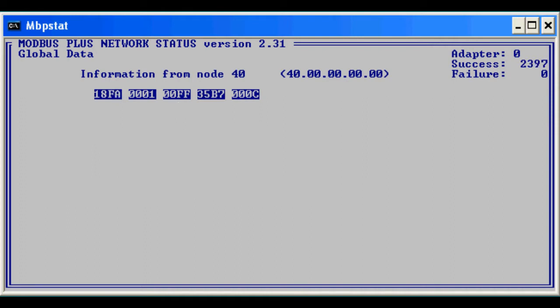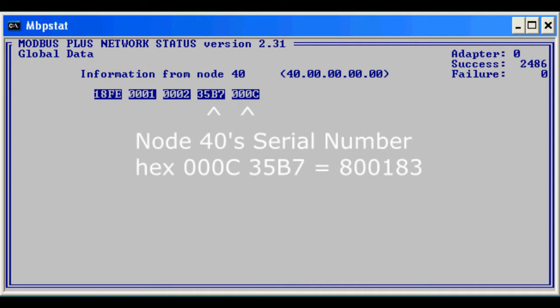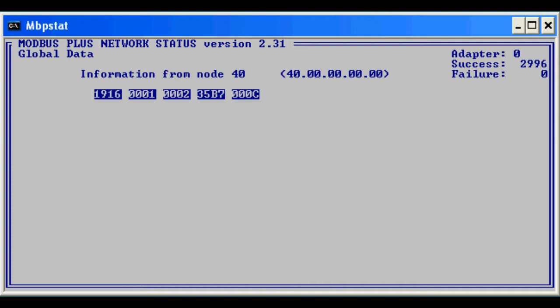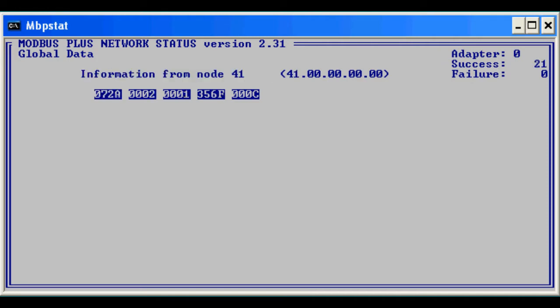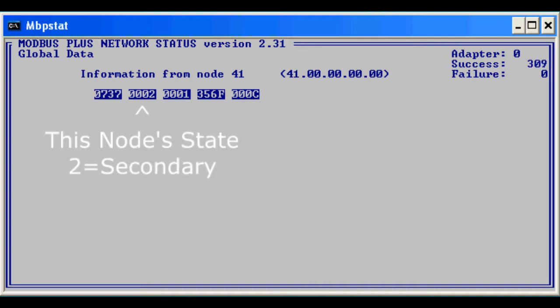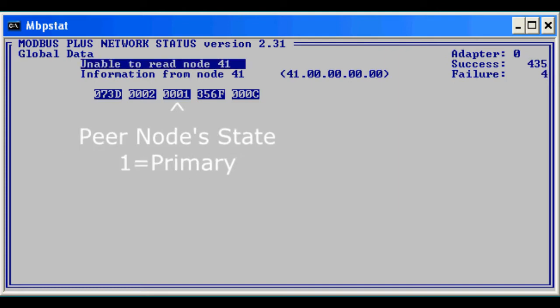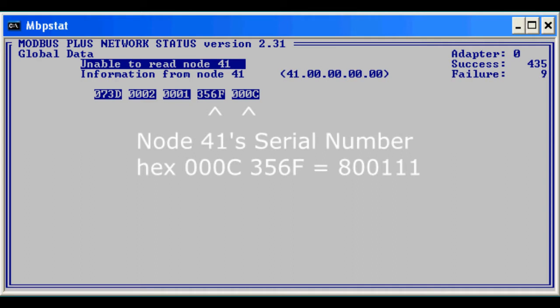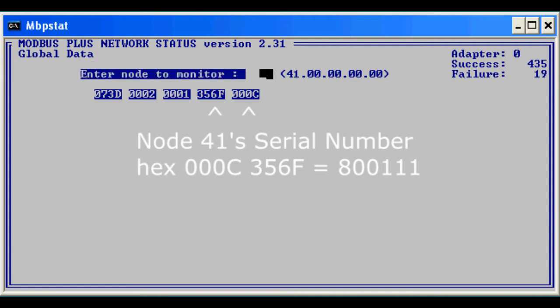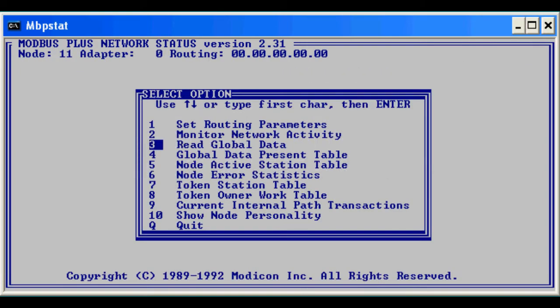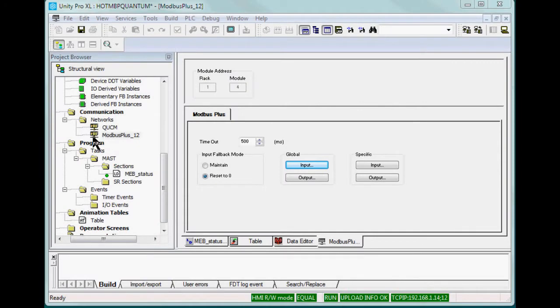The last two words are the serial number of this MEB. Looking at node 41 shows the global data from the secondary MEB. This unit publishes the same formatted data. Unplugging the secondary's Modbus Plus cables interrupt the MBP STAT comms.